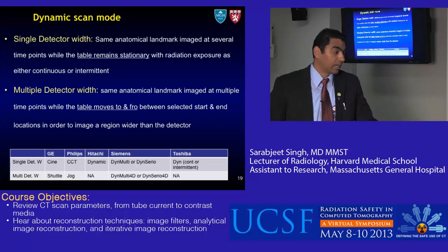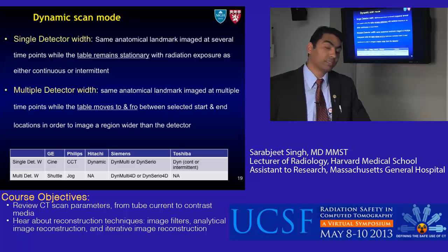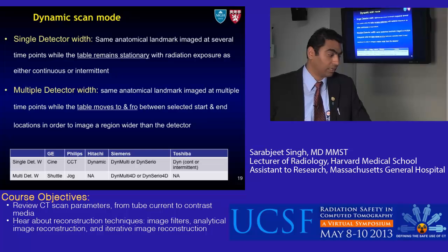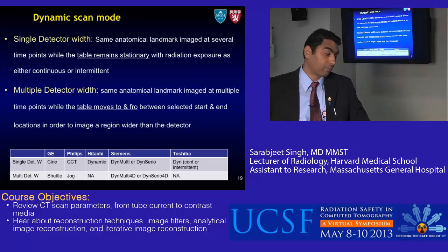Now let's look at dynamic scan mode. In single detector width mode, the same anatomical landmark is imaged at several time points while the table remains stationary, with radiation exposure either continuous or intermittent. In multiple detector width mode, the same anatomical landmark is imaged at multiple time points while the table moves back and forth between selected start and end locations to image a region wider than the detector. Different vendors use different names: GE calls it Cine mode or Shuttle mode; Philips calls it CCT or JOG; Hitachi calls it dynamic; Siemens calls it DynMulti or DynSerio.